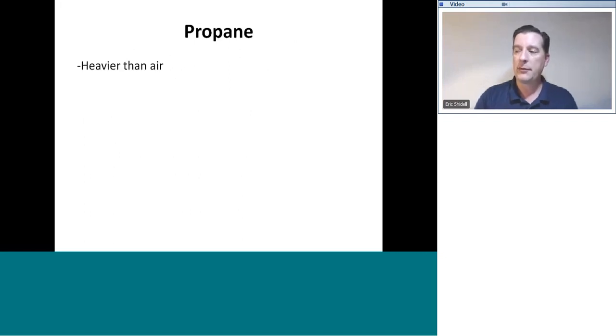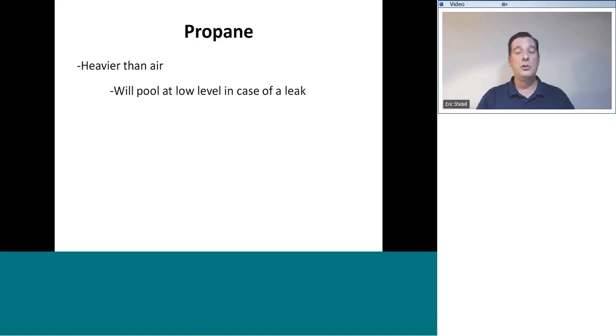Propane, a little different. Propane is heavier than air. Remember when I said that propane has a more complicated molecule? It's a more dense fuel. It's also heavier than air. And as a result, it will pool at a lower level in case of a leak. This makes propane potentially more dangerous than natural gas. It does not mix with air quite as easily as natural gas does. Now, that doesn't mean to say that it's hard to mix with air, but it's not as easily mixed with air as natural gas. So as a result, it can pool into a concentration near the floor.